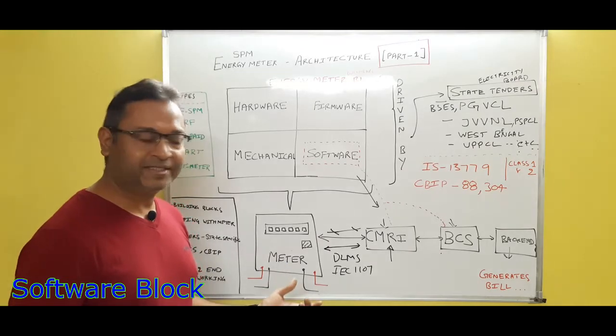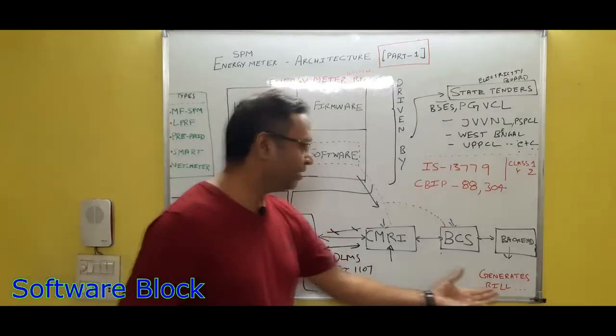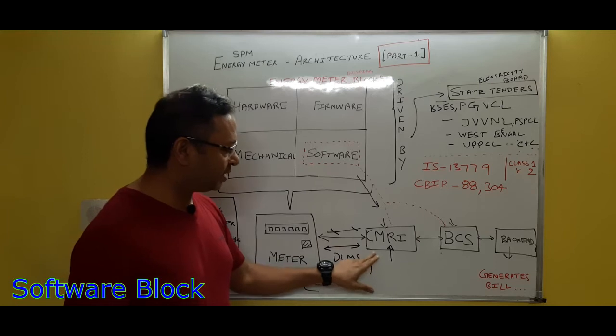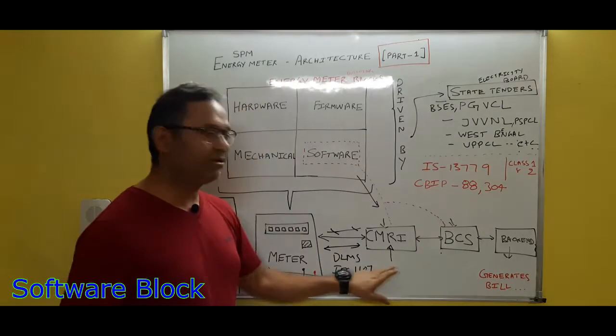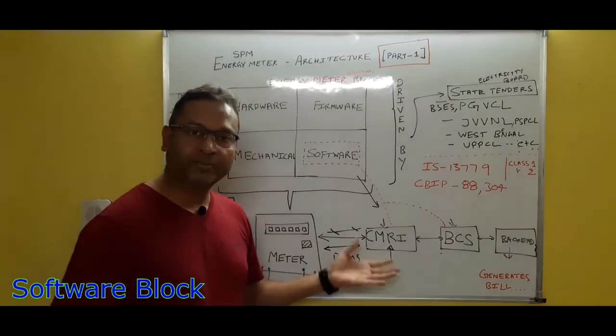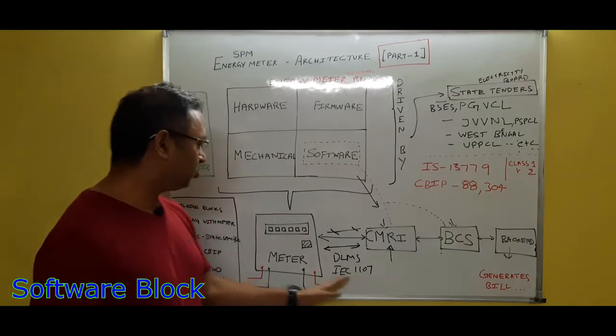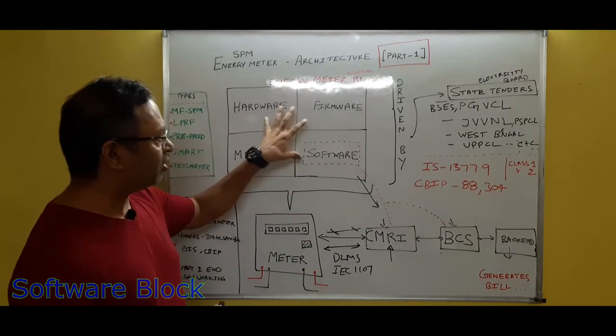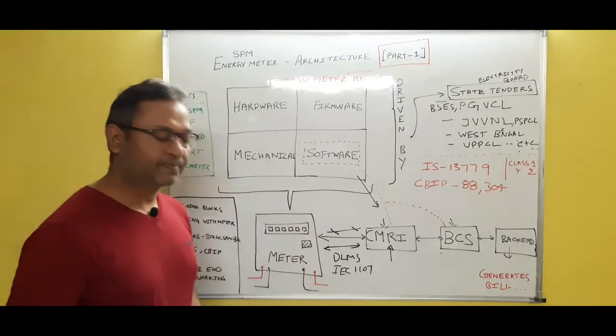This is a kind of a complete chain. Complete chain, I mean to say, you have a meter, then a CMRI unit and the BCS unit, and the back-end software used to generate the bills. So now have some basic understanding about how your meter communicates from starting point to your end point. Now let's talk about the software part. This software part, the software inside the CMRI and the base computer software, is also developed by the manufacturer companies because these softwares may have some proprietary protocol or may have some standard protocols like DLMS or IEC 1107 to communicate with the meter.